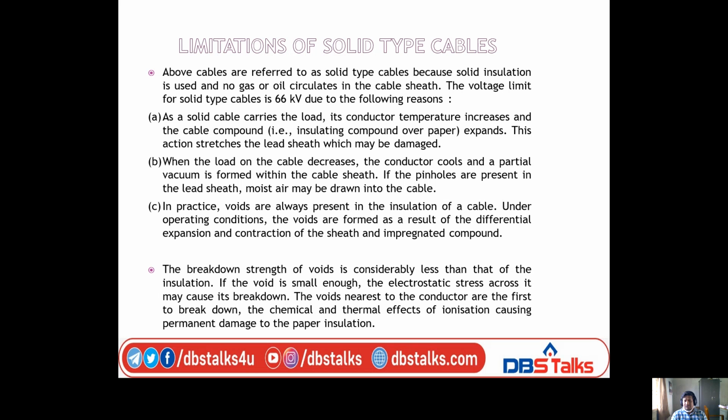Stretches in the lead sheath, right? Suppose load decreases, the conductor cools, and the temperature of the conductor decreases, such that a small vacuum is formed within the cable sheath, and some small moist air may enter into the lead sheath.